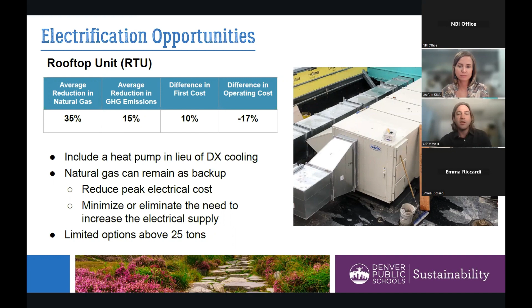This is a summary across rooftop units for all the schools looked at. Sometimes rooftop units can have a very negligible increase in first cost, because when you're adding cooling you've already got DX cooling capacity, and a heat pump is essentially just adding a reversing valve and some controls. Since these are existing school buildings, there will still be natural gas backup, so at a certain temperature rooftop units might switch over to natural gas. This is limited to smaller rooftop units, 25 tons and under, but these are sort of the low-hanging fruit in terms of electrification.